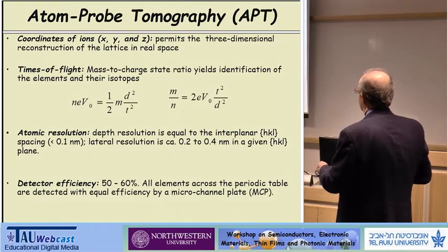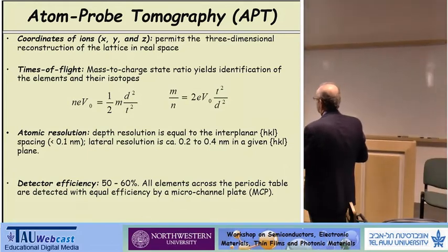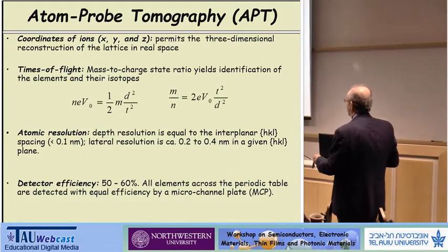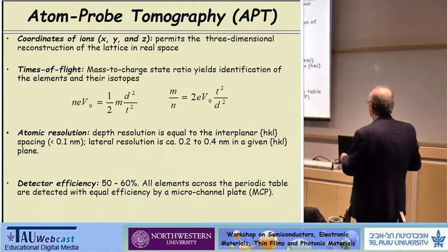The atomic resolution in depth is equal to the interplanar spacing, HKL, and that can be less than 1/10 of a nanometer. The lateral resolution depends on the specific crystallographic plane you look at, and that's between 0.2 and 0.4 nanometers. The current detection efficiency is between 50 and 60%, 57%. And the whole basis of detecting the atoms, the ions, is this microchannel plate.